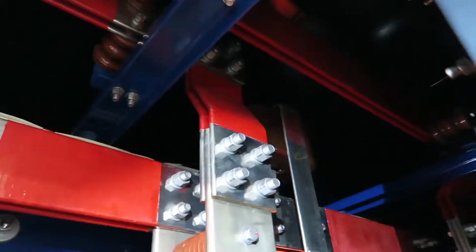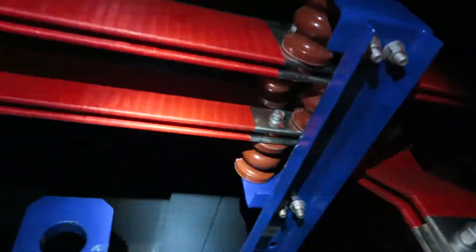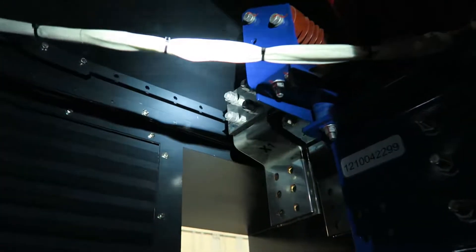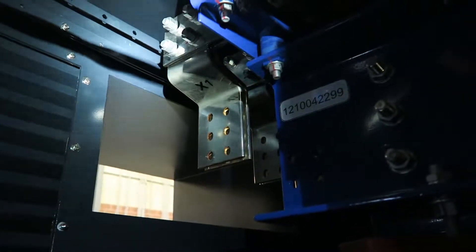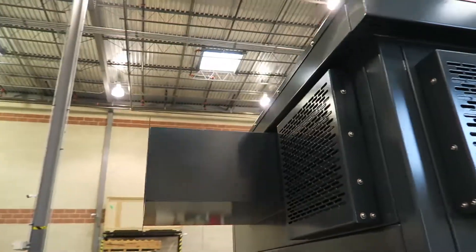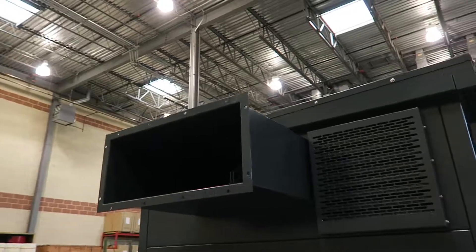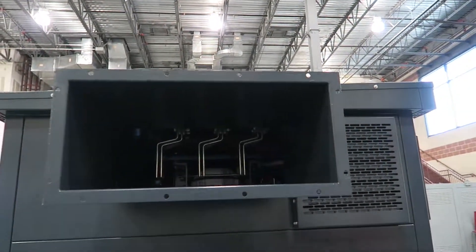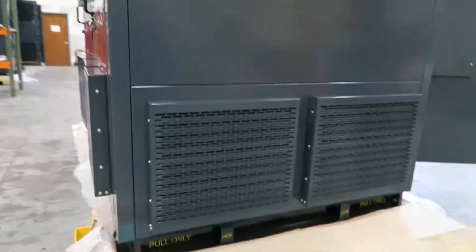That is the secondary bus which travels to the left of the enclosure and ends with the secondary bus terminals. This flange will be made up with secondary switchgear and connections to those terminals will be made via flexible connectors.